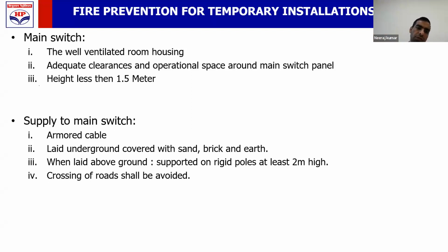So the cable which will bring power to the main switching station, the incoming cable, shall be armored. आर्मर का रिक्वायरमेंट इज नॉट देयर फॉर अदर केबल्स जो आपकी वेल्डिंग और ग्राइंडिंग मशीन का है. It is only for the incoming cable. This cable shall be laid underground, covered with sand and brick.